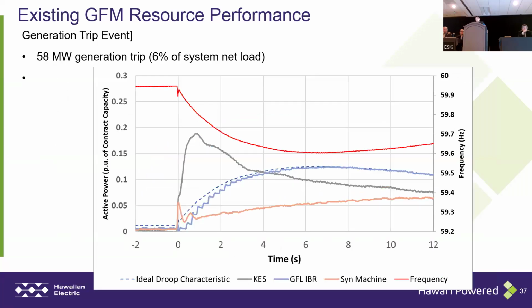This is the second generation trip event. The magnitude of the generation trip is smaller, around 6% of the system net load. The purpose of this slide is to compare different resource responses. The red curve is the system frequency, with the axis on the right side. It was not reaching 59.4, so there's no FFR triggered.